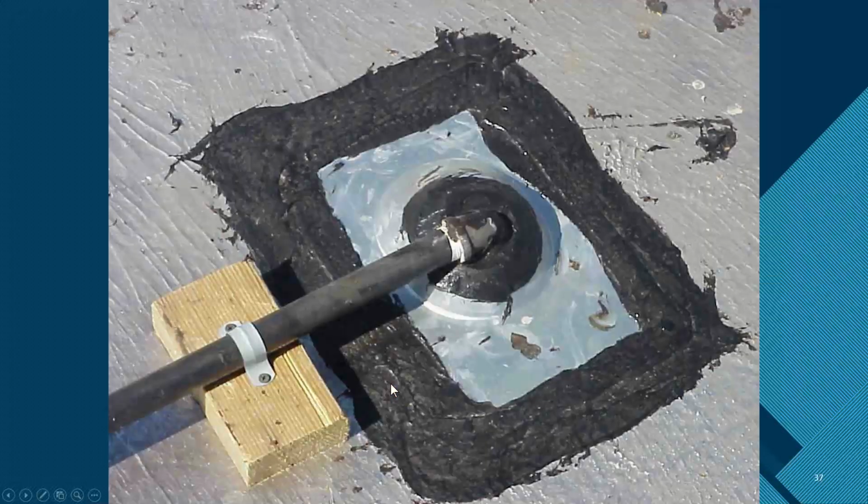Hey, Brick, would you write up the white tape needs to be replaced with yellow tape? I would not. It's no different. It's just one extra wrap. I would make a statement that we need to verify that they did a pressure test for this new gas line. If one doesn't exist, they'll have to have a pressure test during their inspection.